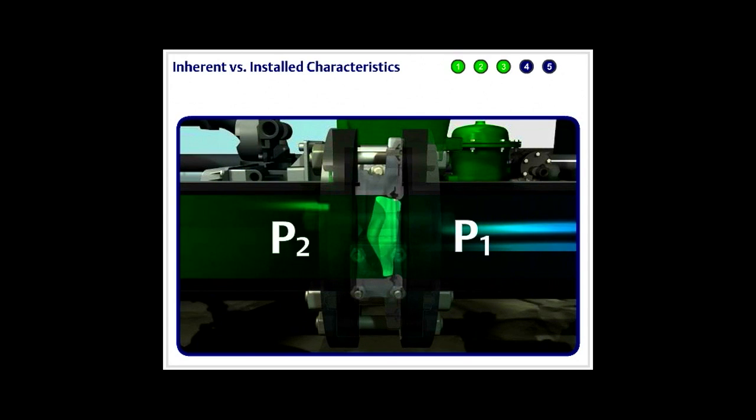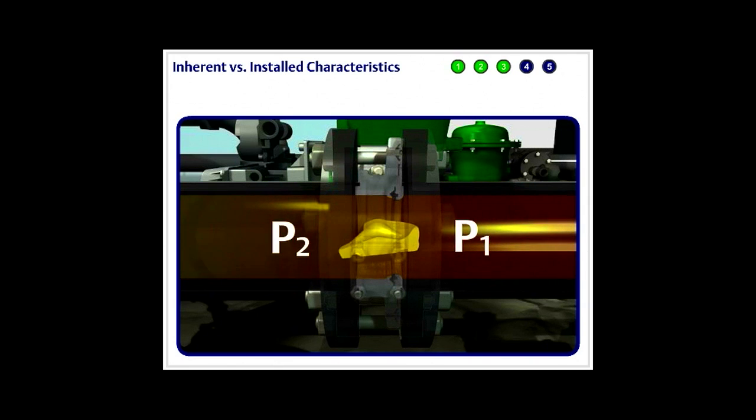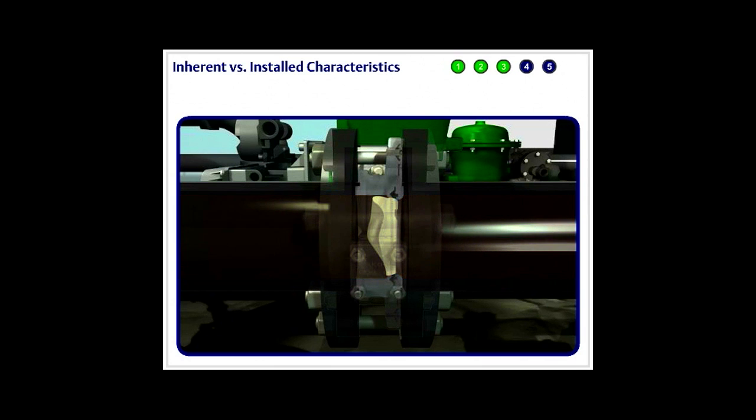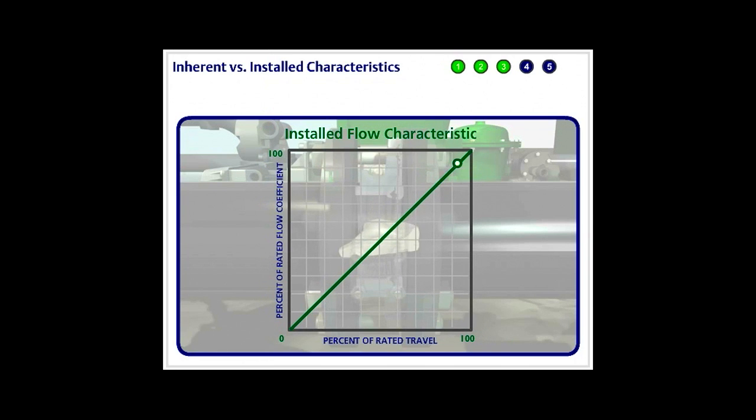While the inherent flow characteristic is important for sales catalog purposes, it is the installed flow characteristic that is important to control of the process. The installed flow characteristic determines to a great degree just how well the valve will perform against changes in pressure and flow. It is important to note that the control disc's inherent equal percentage flow characteristic translates into an installed linear flow characteristic.